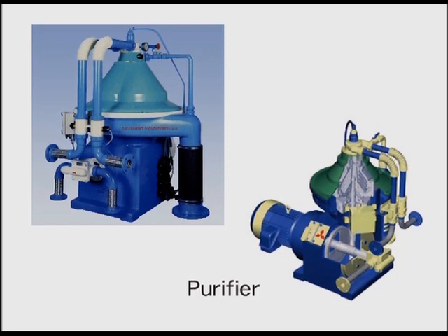Select the purifier based on gravity disc selection procedure described in the operation manual of Purifier. The appropriate interval for discharging the sludge varies with the quantity of the mixed-in insoluble content, so adjust the interval for discharging after having checked the degree of dirt of the bowl.